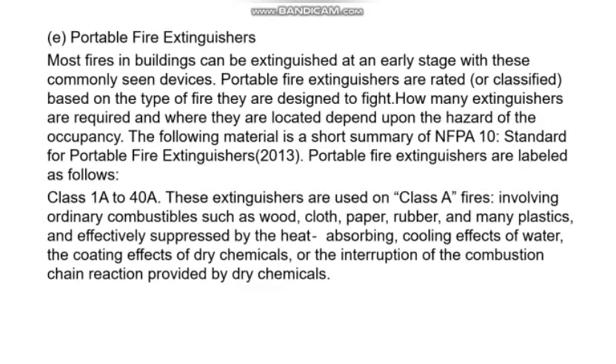Next is portable fire extinguishers. Most fires in buildings can be extinguished at an early stage with these commonly seen devices. Portable fire extinguishers are rated or classified based on the type of fire they are designed to fight. How many extinguishers are required and where they are located depend upon the hazard of the occupancy. The following material is a short summary of NFPA 10, standard for portable fire extinguishers. Portable fire extinguishers are labeled as follows.